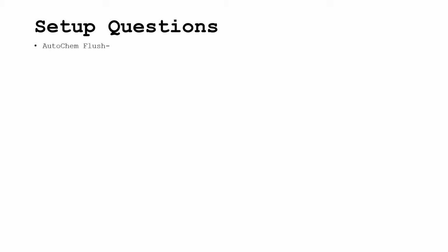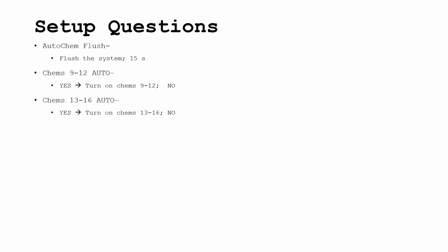AutoChem flush: the amount of time the system will flush the system with water after each chemical injection, recommended, 15 seconds. Chems 9 through 12 auto: if answered yes, the system will turn on the chemical outputs for chemicals 9 through 12, recommended, no. Chems 13 through 16 auto: if answered yes, the system will turn on the chemical outputs for chemicals 13 through 16.